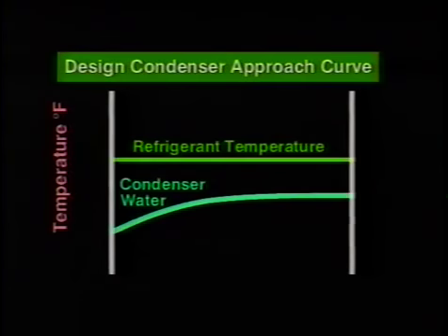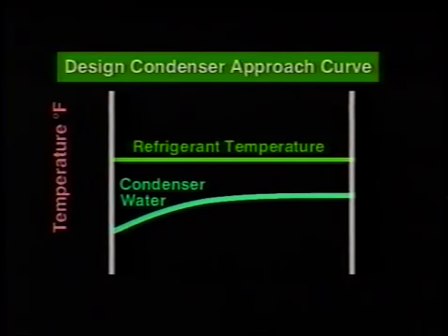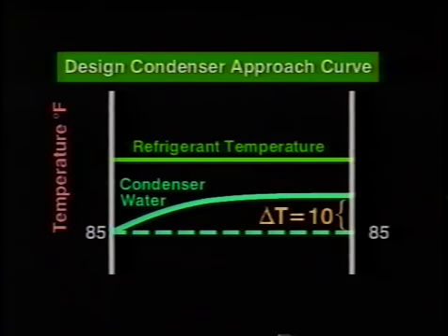Like the cooler, similar approach curve relationships exist with a water-cooled condenser, except that the water leaves hotter than it entered, since it's absorbing heat from the refrigerant. A typical cooling tower installation would provide water to the condenser at 85 degrees Fahrenheit, and the typical 10-degree rise will give us leaving water at 95 degrees.